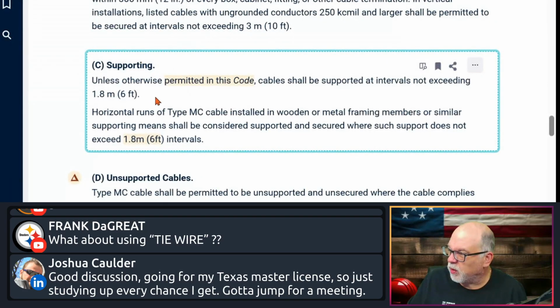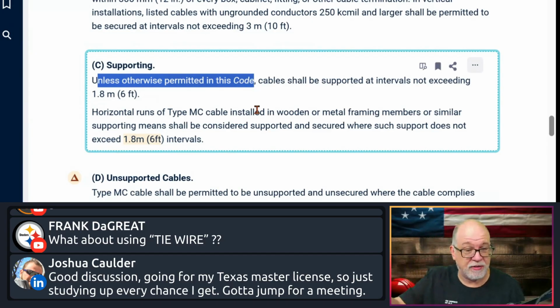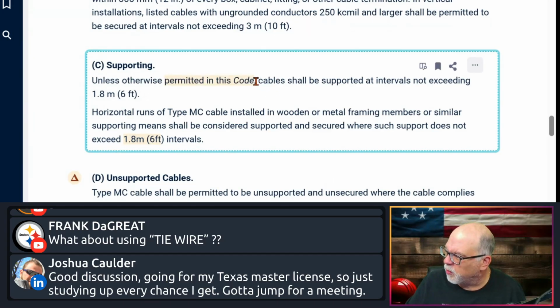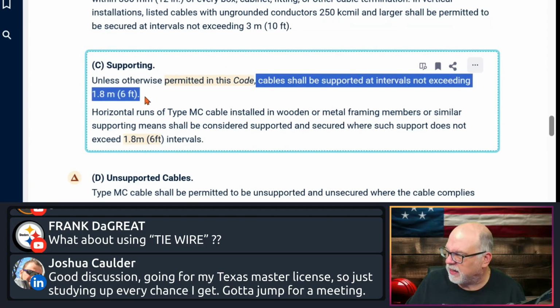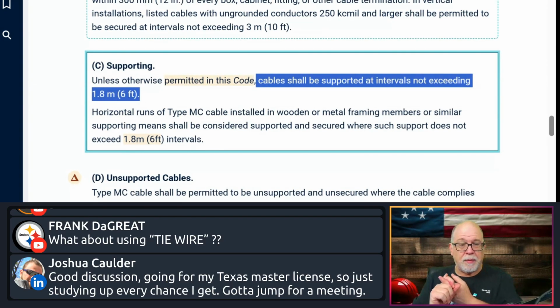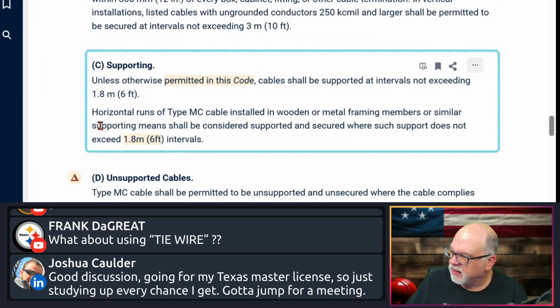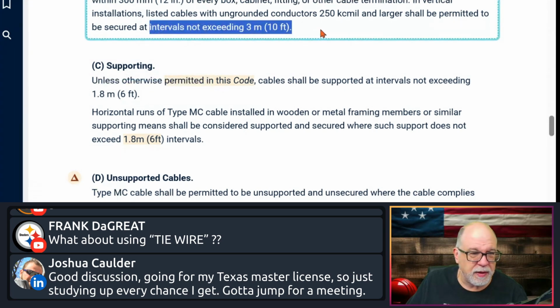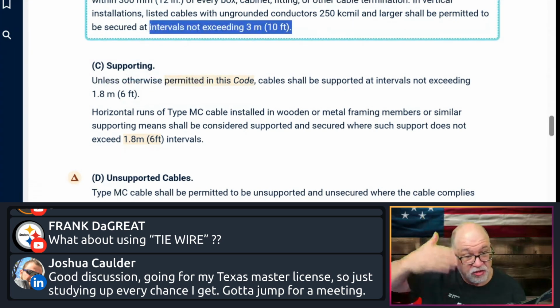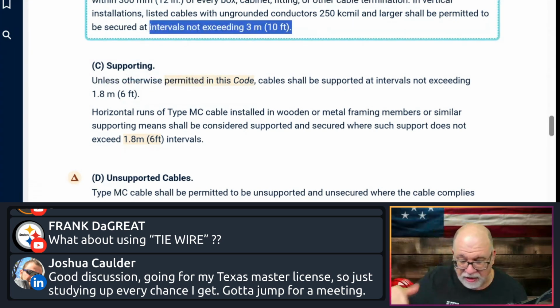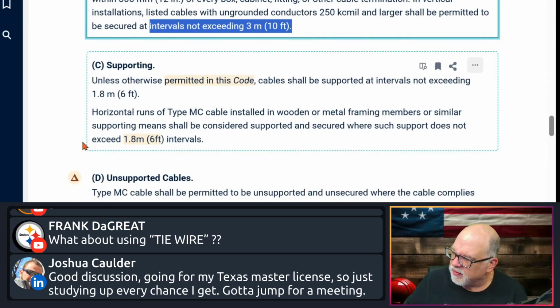All right, so supporting, unless otherwise permitted in the code, again, would be the unsupported lengths as an example. It says, for supporting, it shall be supported at intervals not exceeding 6 feet. So see, these are pretty easy to remember. Secured every 6 feet, supported every 6 feet, okay? Now, it goes on to say, again, unless otherwise permitted, okay, which we have some otherwise permitted rules up here, vertical application, 10 feet, depending on the conductor sizes.